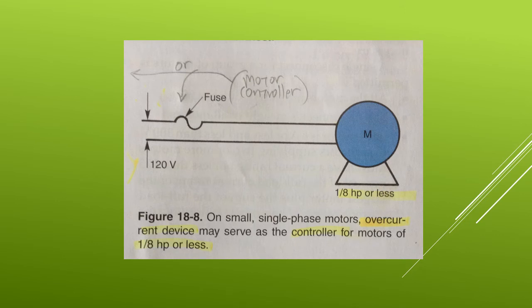Controller requirements. Motors must be provided with some type of control. The NEC defines a motor controller as a switch or other device normally used for starting and stopping a motor. The controller must be protected against short circuit current damage. There are numerous options available to meet the requirements. The method used depends primarily on the size and type of motor.